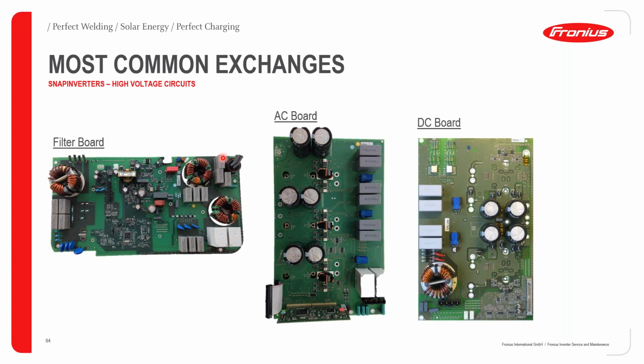On the right-hand side of this filter board is where we find the AC filtering circuits. This part of the circuit is responsible for filtering your sinusoidal signal, which is coming from the AC board, ensuring that you have a harmonic that does not have a lot of subharmonics on it. So you have a nice clean signal, which will then be supplied to the load.